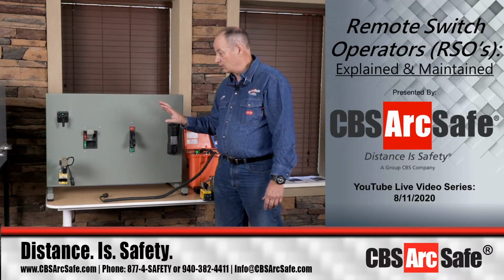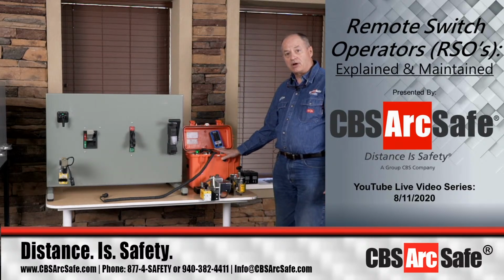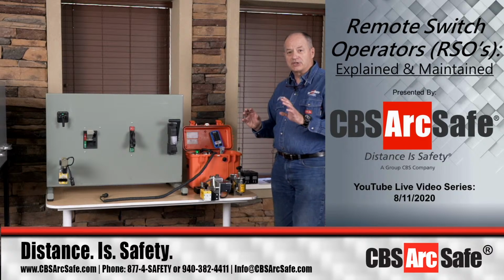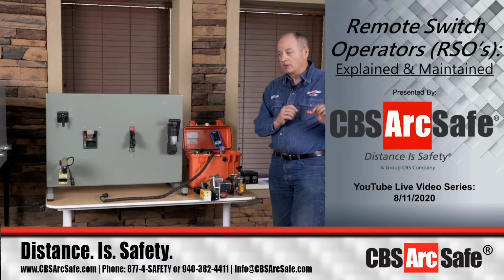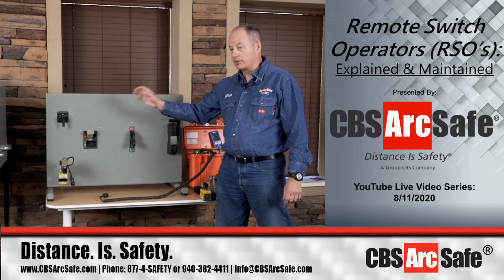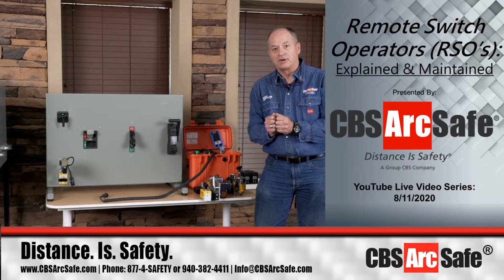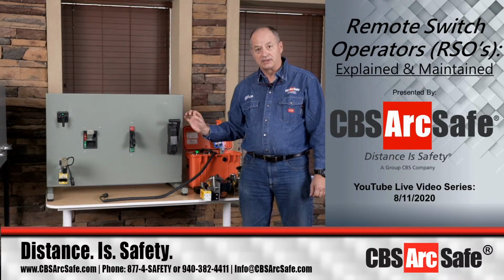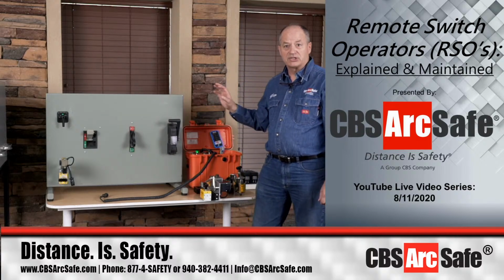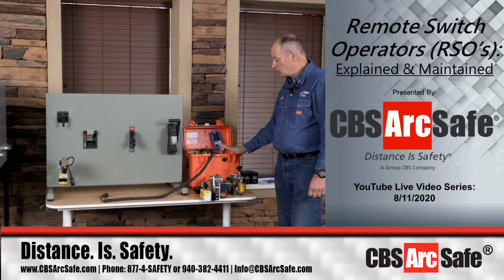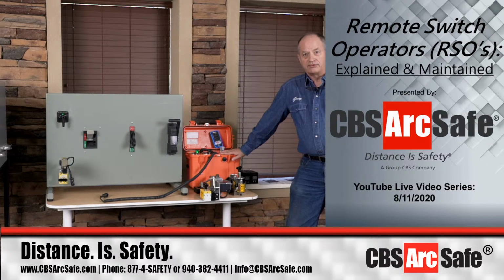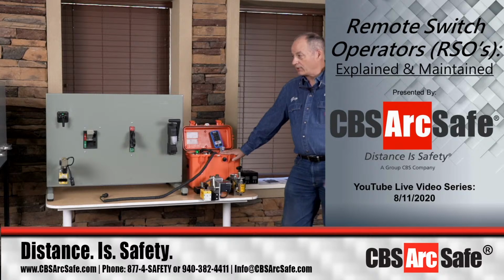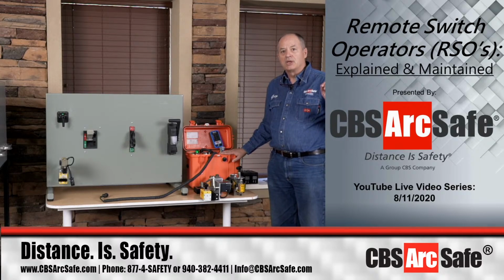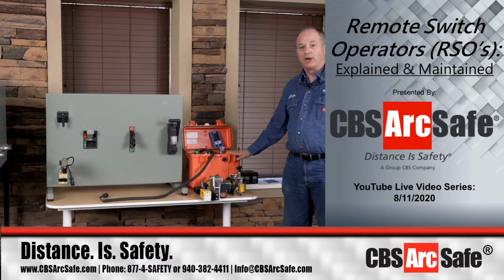So I can use different actuators with one control box and make all of these systems work. The difference between this and our Martech line is, they're made for just one specific function, like a push button or a control switch. So if you have something in that line of our equipment, it's only going to be able to operate one thing, instead of having a family of actuators where I may need to operate several things with a single control box. The RSO-I AR can operate over 300 different actuators, whether it's molded case circuit breakers, push buttons, control switches, motor control centers, medium voltage switches like HVL, HVLCC, GE, or PowerCon load break switches. All of those can be operated with one RSO-I AR.